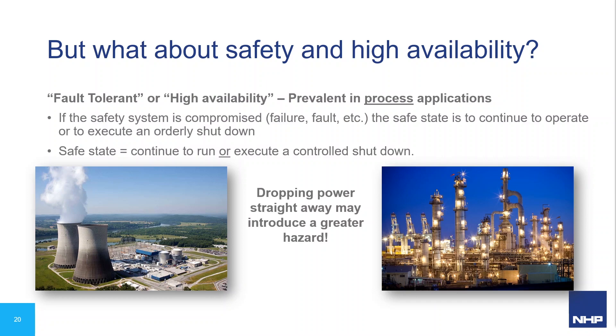This is called high availability — where simply shutting off could create a more dangerous situation, particularly in the process industry. Take a pressurized vessel where pressure is carefully controlled by an electronic valve: if we shut everything off due to a detected fault, the valve de-energizes, pressure could build to dangerous levels, and the vessel could rupture. Instead, a safe state might be to continue running whilst a replacement is sourced, or perform a controlled shutdown. Machine safety also requires careful consideration of what happens when the e-stop is pressed — simply dropping power immediately might not be best.